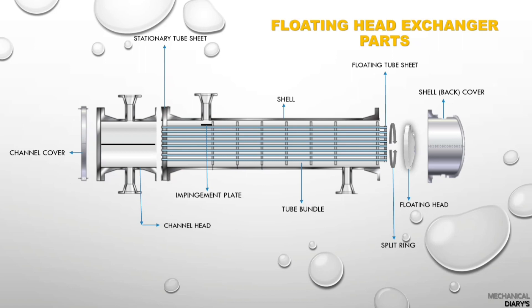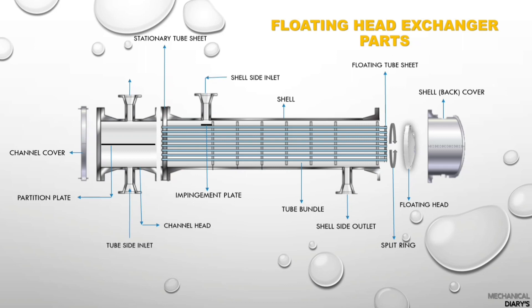One more important part is called the impingement plate. This plate is always placed on the shell side inlet nozzle, because the inlet pressure should not affect the tube bundle directly — that is why it is placed on the shell side nozzle area. Next is the channel head partition plate, which is used to divert the flow from one end to another.